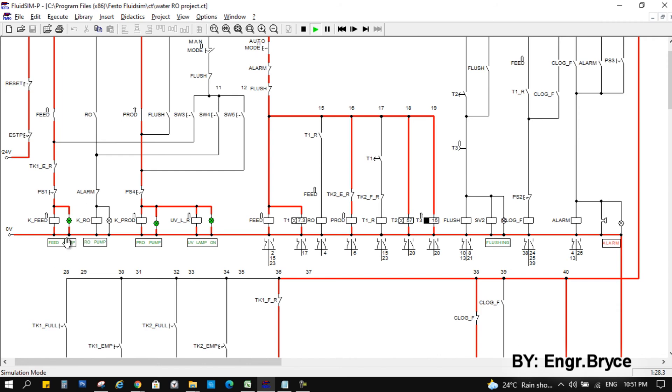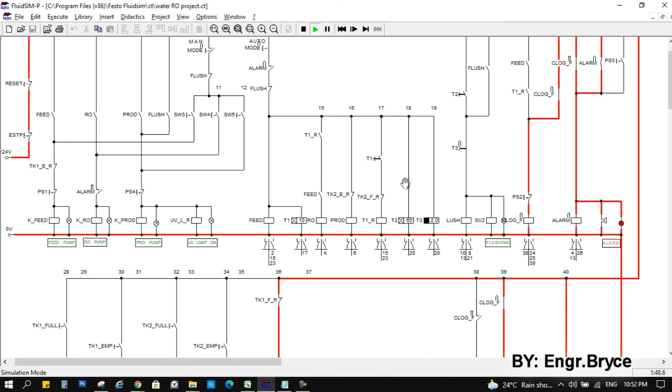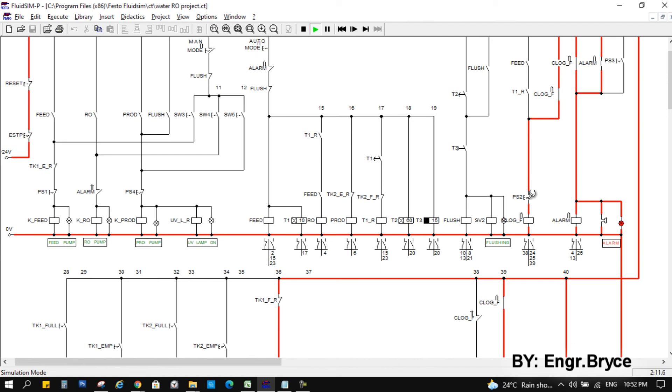Automatic mode immediately starts the feed pump if all conditions satisfy. So it has a timer here to monitor if it will build a pressure in the suction line of the RO pump. If no pressure build up, it will immediately trigger the alarm, turn off all the pumps. So it's like a safety feature. It will not damage also our RO pump. And it is like a monitoring if there is a clog or closed valve somewhere in the filter section. So yeah, let's see we have pressure already.